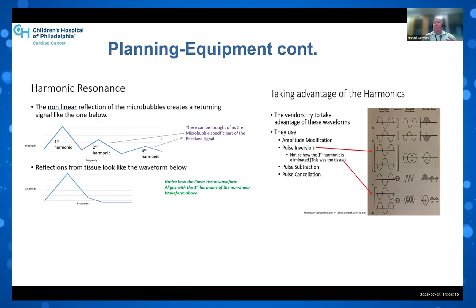So why that matters is, depending on the vendors, the pediatric transducers do not have the factory built-in contrast button that I have set on right there. So if you're going to try and use a high-frequency transducer, and somebody has a suggestion of, let's just turn down the mechanical index to avoid cavitation, you will avoid cavitating of the bubbles, but the image will not be as beautiful as using a contrast setting where you're going to do things like turn on pulse wave inversion. So when you start making these protocols and these settings on your machine, be aware you might have to scan with adult transducers with adult settings that have the factory contrast settings on the machines.